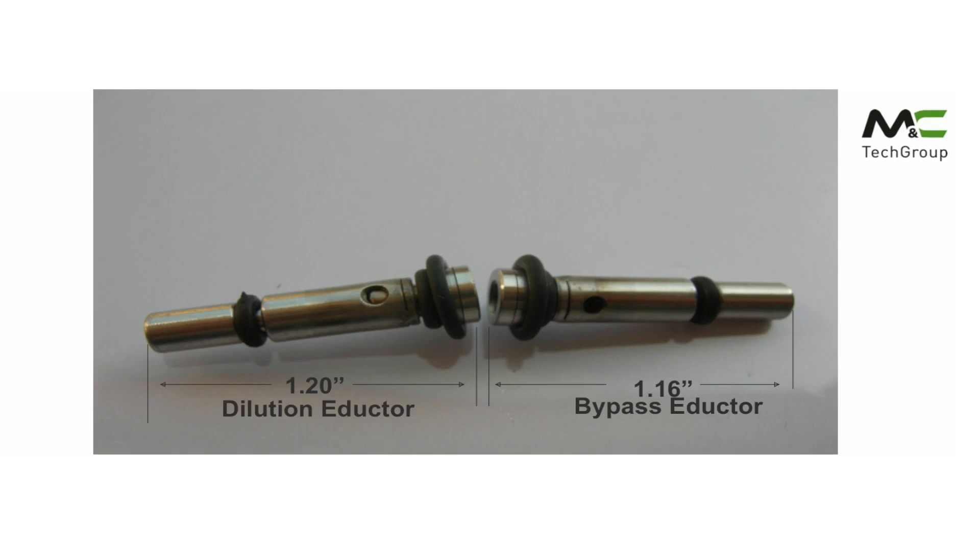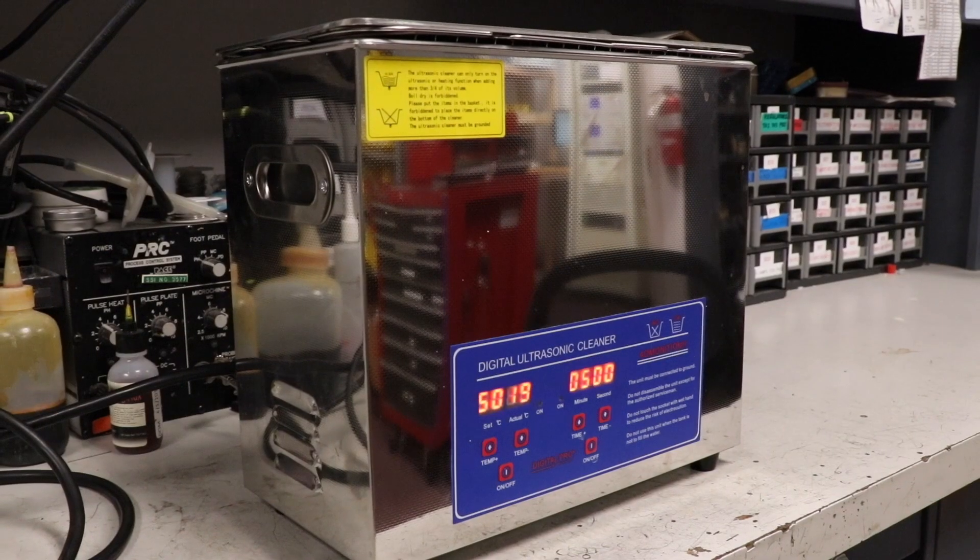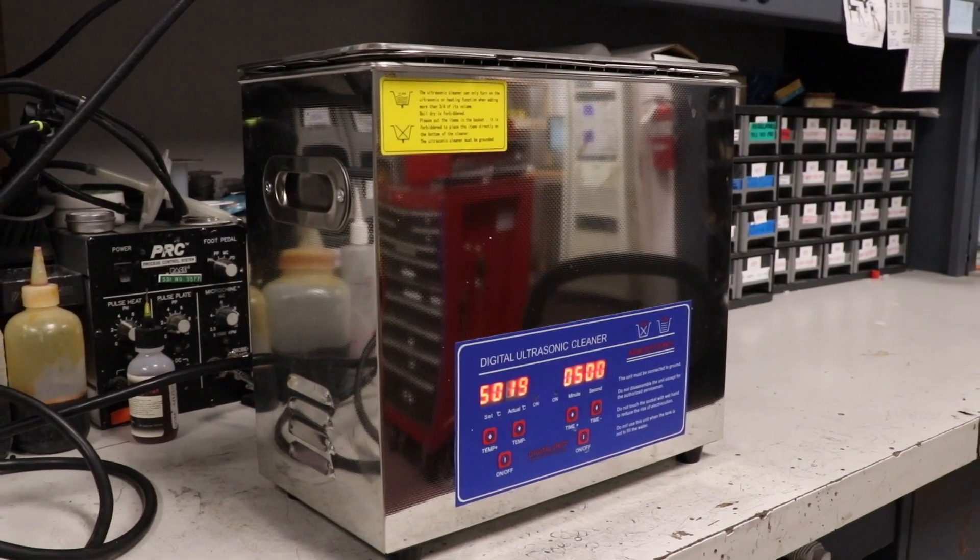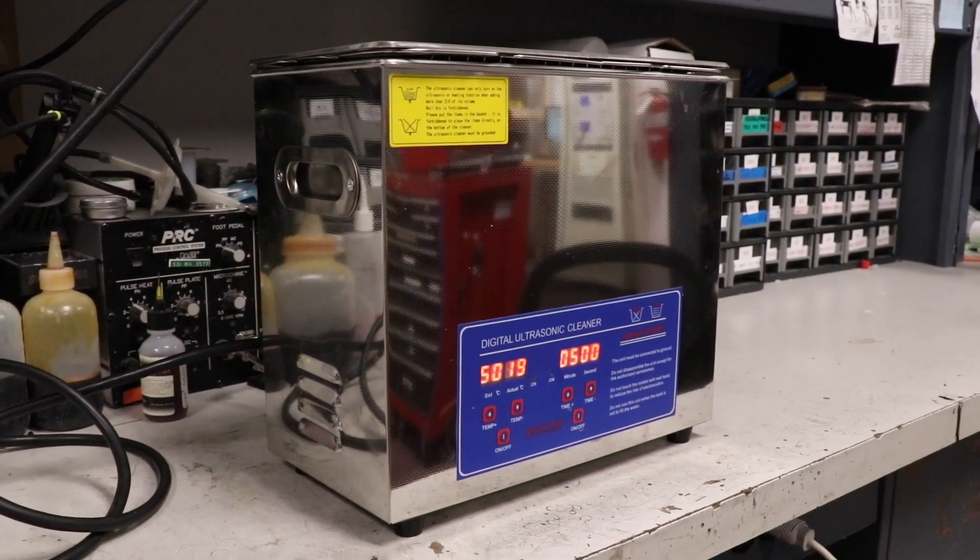We recommend rebuilding these blocks one at a time as the dilution and bypass eductor are not interchangeable. Do not clean these pieces mechanically. Clean the orifice and the eductor in an ultrasonic bath.